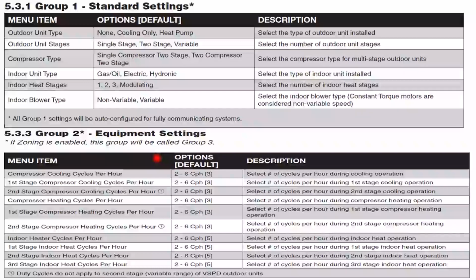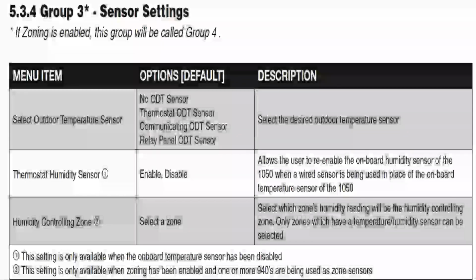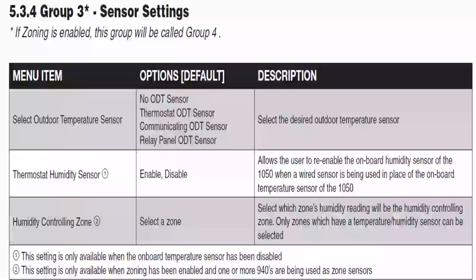Group 2, equipment settings. You're just going to leave these in default unless we start needing to change things, but hardly ever do we have to change the cycles per hour. Group 3 is your sensor settings. Select outdoor temperature sensor. This is where we're going to select, do we want to use the outdoor sensor in the outdoor unit, or do we want to use online weather, or did we wire in a separate outdoor sensor to the relay panel?